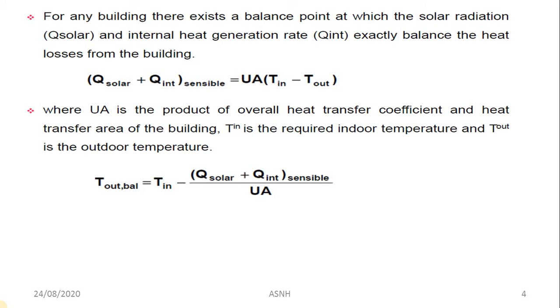Now the method of estimation. Generally the heating and cooling load calculation involves a stepwise procedure taking into account all the building energy flows. Take the example of a commercial building. First of all, we must read the drawing of that building, then the location, region, facing, and the direction of the sun radiation. After that we must consider the U values of the various materials used for construction of the buildings. Similarly, we must consider the sensible and latent heat gain factor.